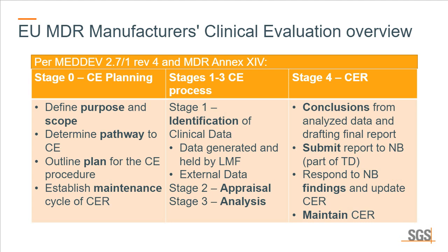And in the past, we had problems with some manufacturers who built on such shaky foundations, and in the conclusion section of their clinical evaluation report, they didn't mention that there's any uncertainty. And in the past, that was maybe their justification of not having a post-market clinical follow-up. So just make sure that if there are uncertainties in the incoming or input clinical data, that you faithfully represent those uncertainties in your conclusion as well, and handle those uncertainties by requiring a higher level of follow-up.